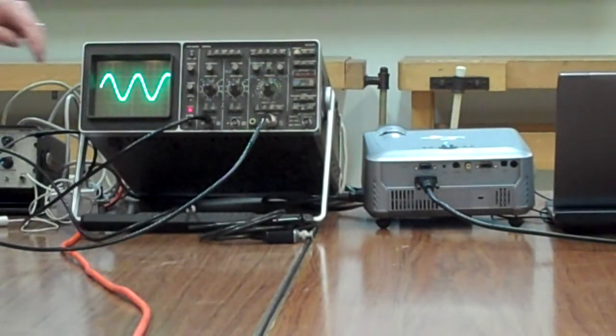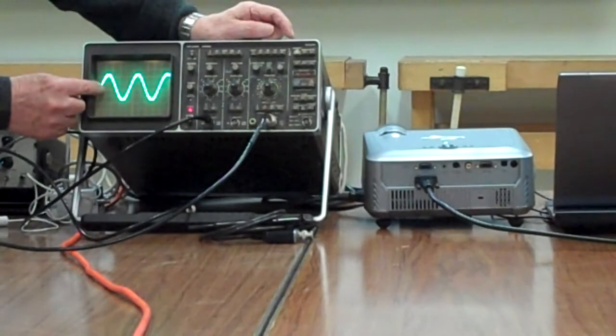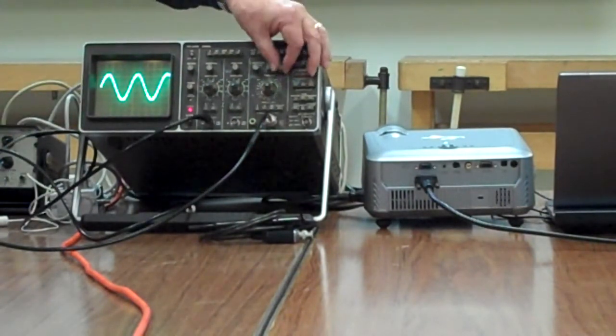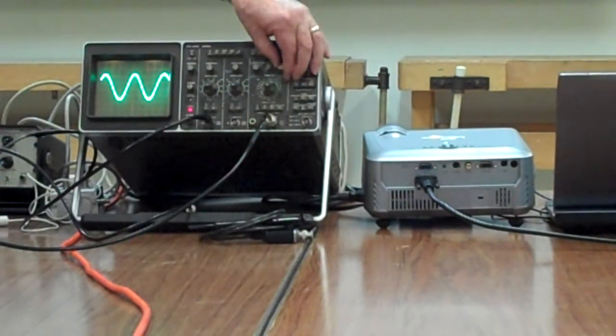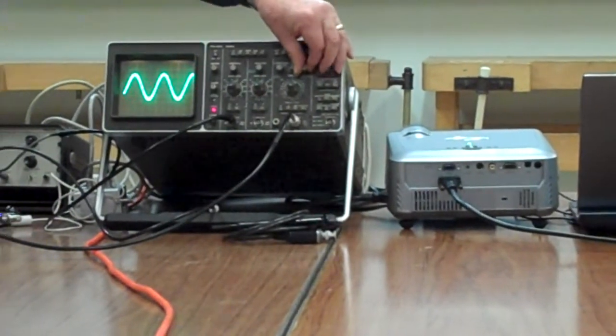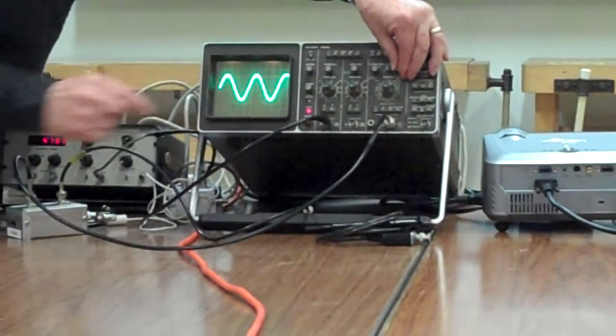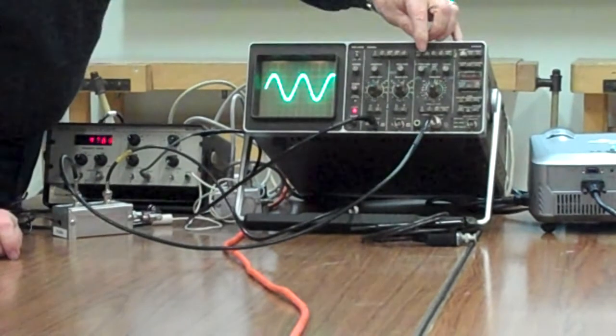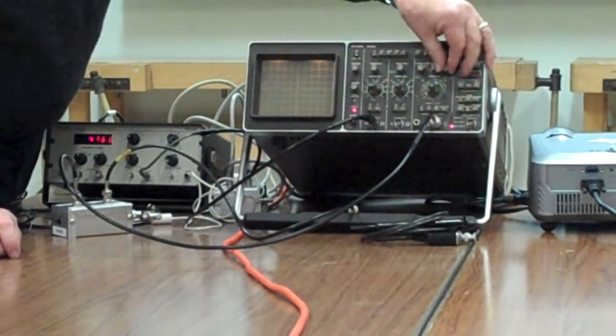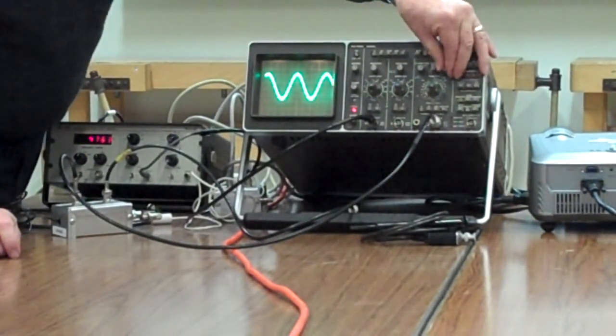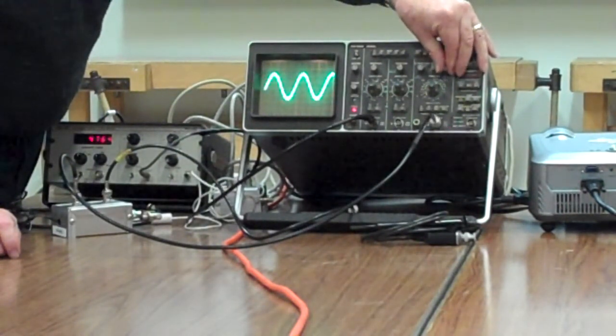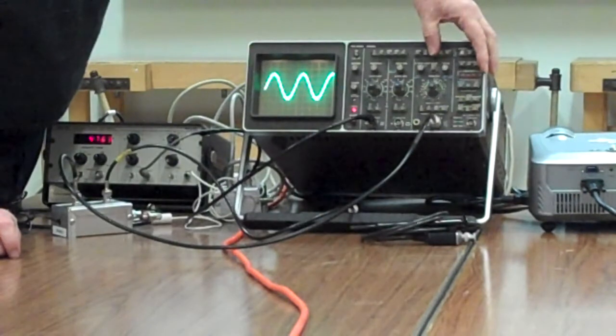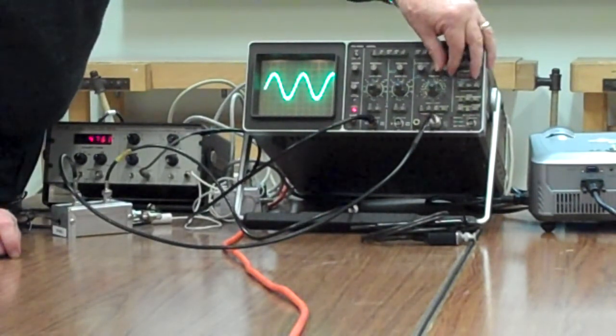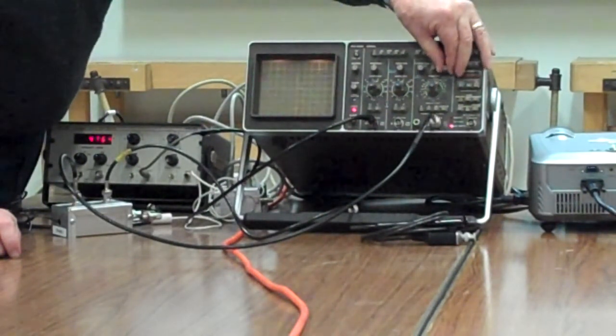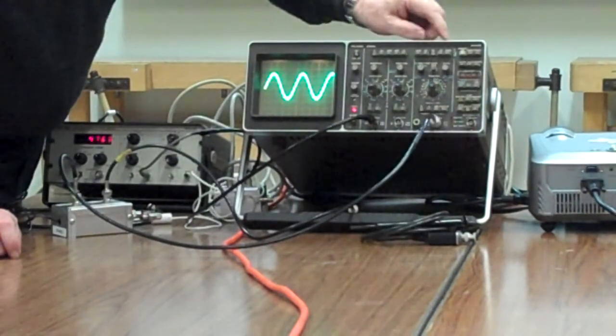Over on the triggering here, we have the level control, so as I move that up and down, you see it moving up and down on the trace itself. If I put it in AC mode, I can trigger on the trace itself, but if I go outside of that, the triggering quits unless we're in auto mode. In DC mode, it should look about the same as far as triggering goes.